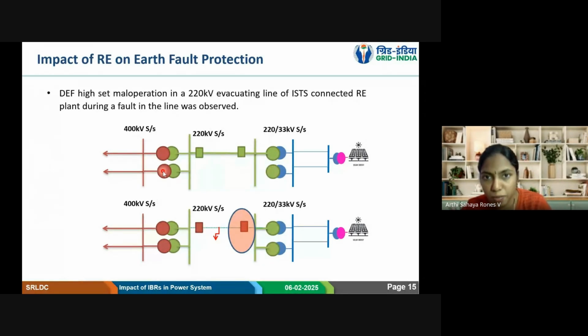During that time also, we have seen the presence of zero sequence current, and there are many literatures on the tertiary contribution of transformers. So meaning that even though the system is radial, through the tertiary of the transformer, we are seeing these currents and impacting the protection. And a few vendors are coming up with adaptive protection schemes. They are taking this itself as an advantage. Instead of sensing the negative sequence component, the relay logics are being changed by sensing the zero sequence components. So those kinds of literatures are also available.